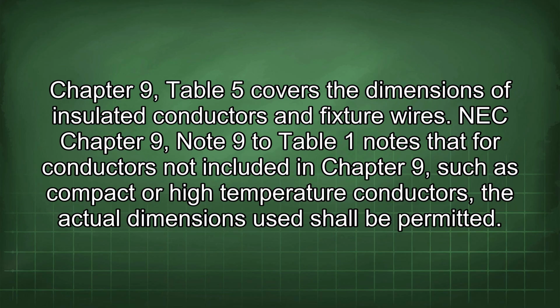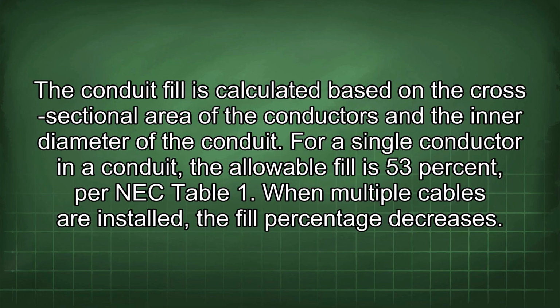NEC Chapter 9, Note 9 to Table 1 notes that for conductors not included in Chapter 9, such as compact or high-temperature conductors, the actual dimensions shall be permitted to be used. The conduit fill is calculated based on the cross-sectional area of the conductors and the inner diameter of the conduit. For a single conductor in a conduit, the allowable fill is 53% per NEC Table 1. When multiple cables are installed, the fill percentage decreases.